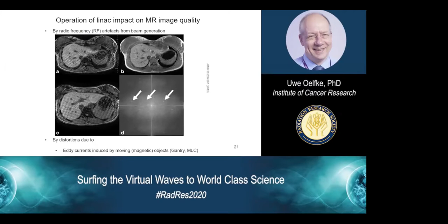Now, what are the solutions to this mutual interference of LINAC and magnetic resonance scanner? First, you can think of a spatial separation of treatment and imaging device, or you use alternative radiation sources like cobalt, for instance. The more sophisticated solution is to optimize the electron guns, shielding all these parts of the linear accelerators from the magnetic field as best as you can. And where you cannot shield it anymore, then you have to generate a low magnetic field zone at the location of the linear accelerators. All these concepts have been used for the devices I will introduce in the next section.